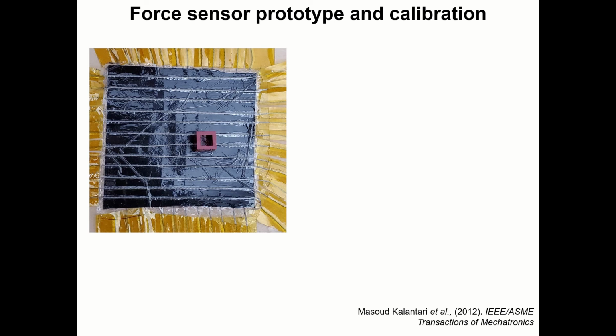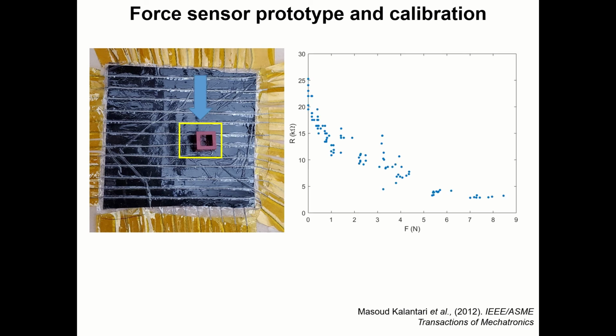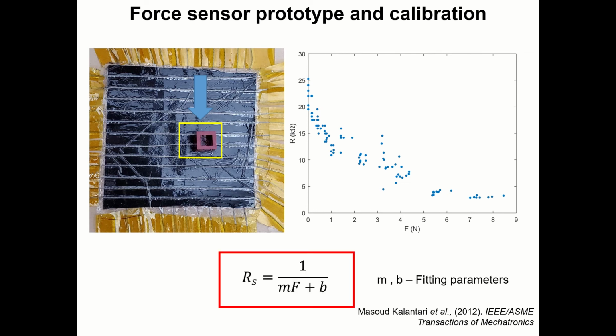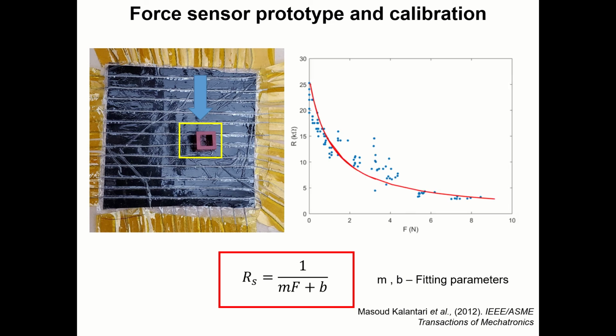For the calibration process, we applied known forces using standard weights, varying them to calibrate the sensor over a broad range of forces. Using the resistance-force relationship derived from a physics model of a piezoresistive sensor, we fit the data to get the calibration parameters.